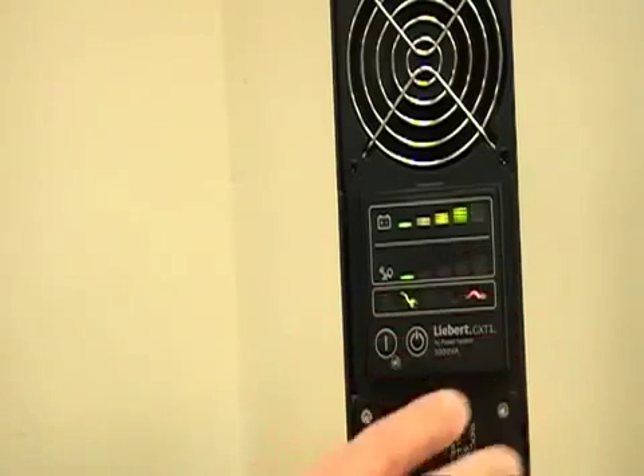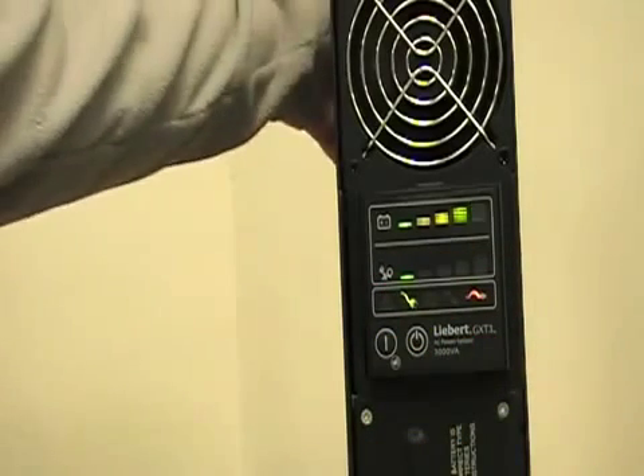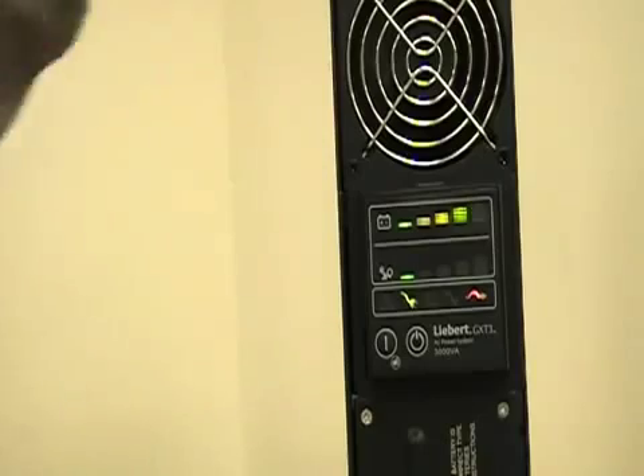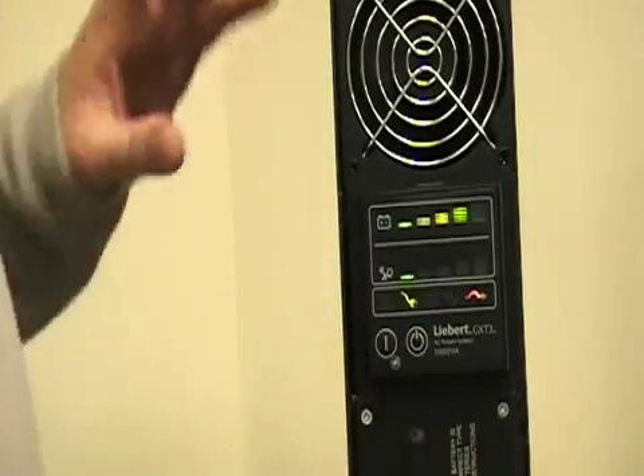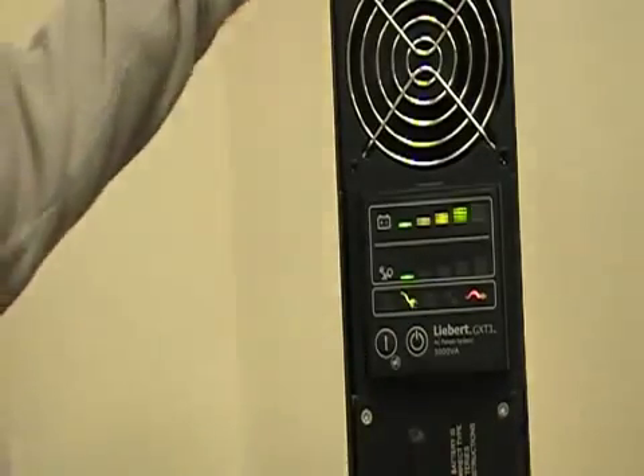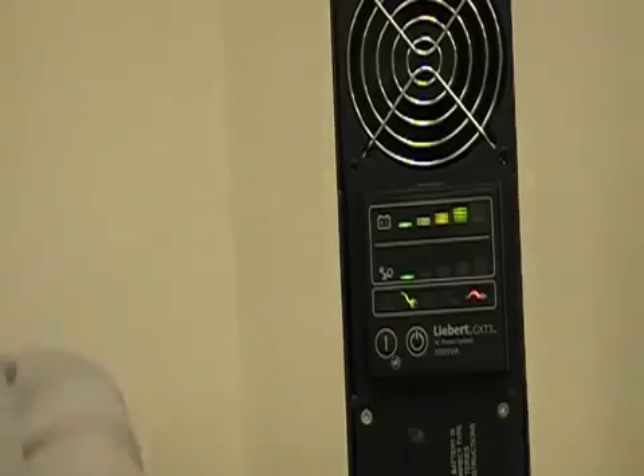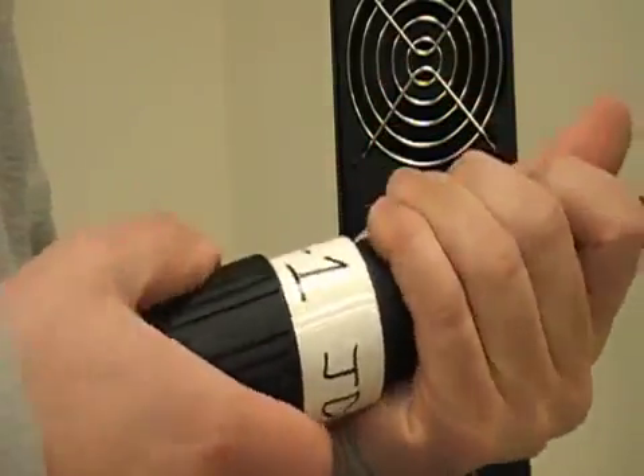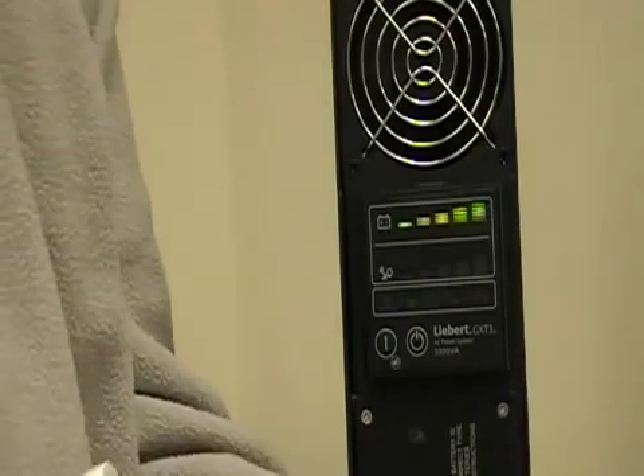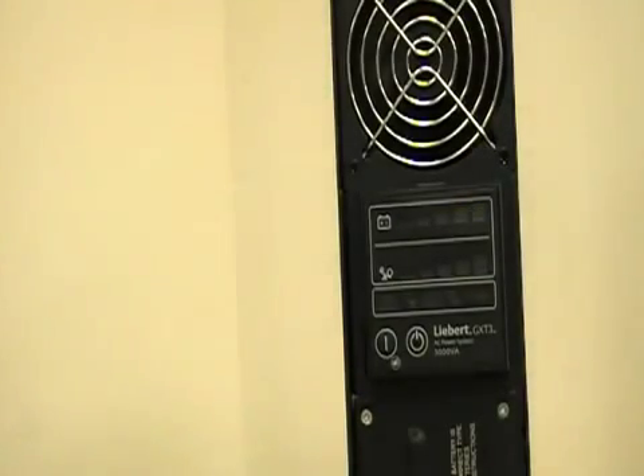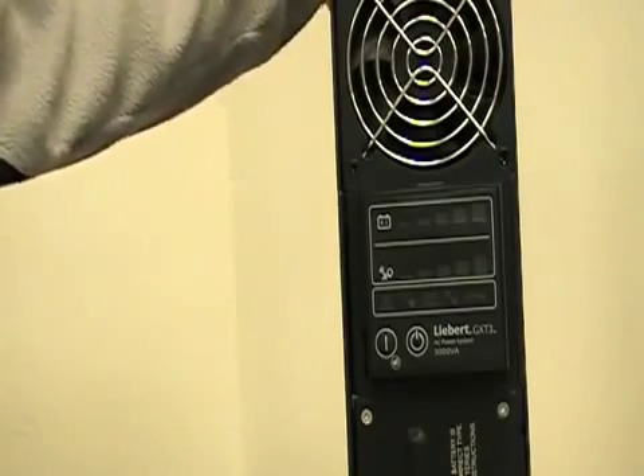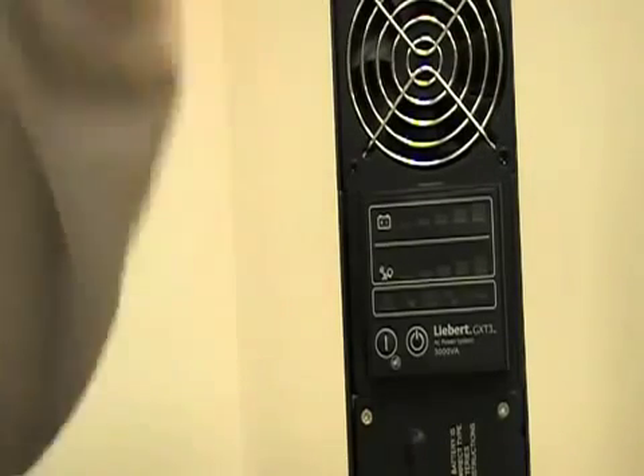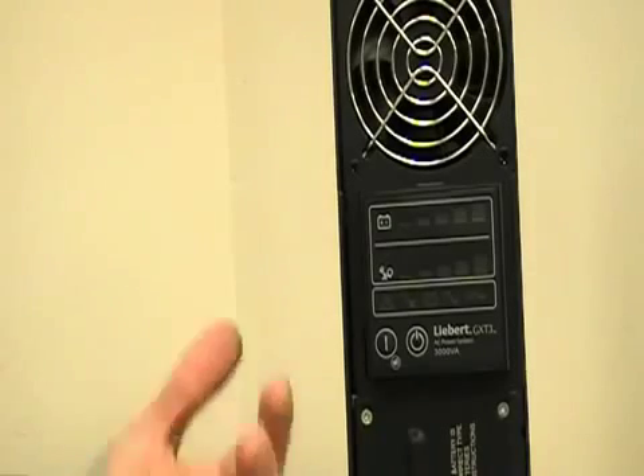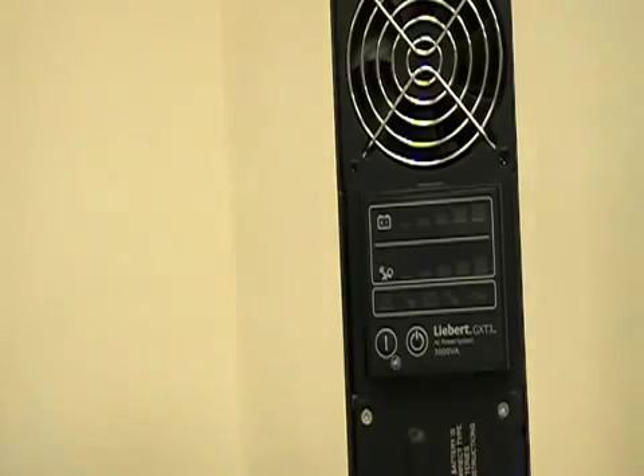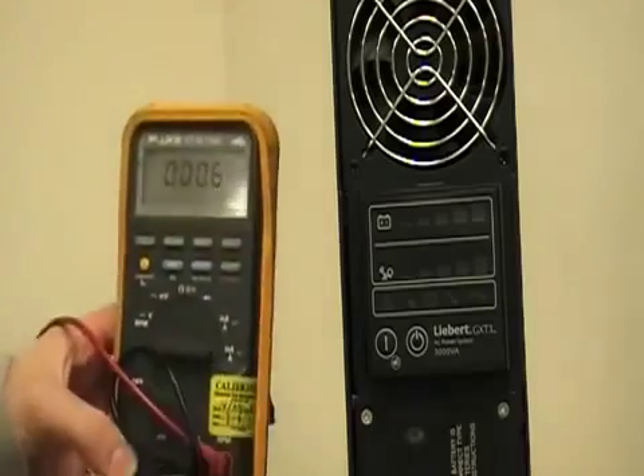At this point, sometimes the back of the unit is not accessible. So what I recommend is, if you don't want to unplug the unit and get all the covers off because you can't get to the main bus, you can just go ahead and unplug the unit at this point, and that'll kill everything. Sometimes you can't get to the back of the unit due to the covers, and the bus might be hot. So we transferred to bypass, we kill the unit, the output's dead, my output here is now dead.